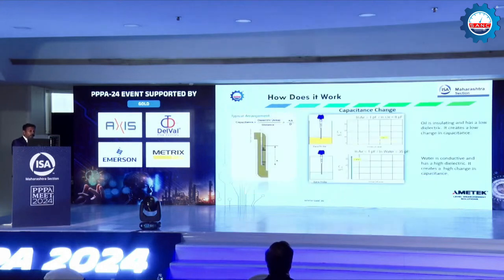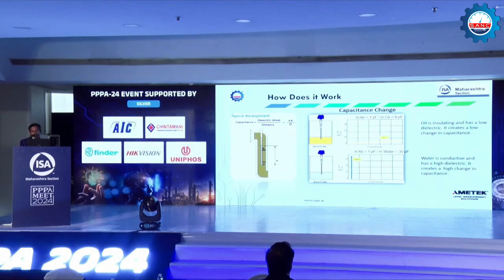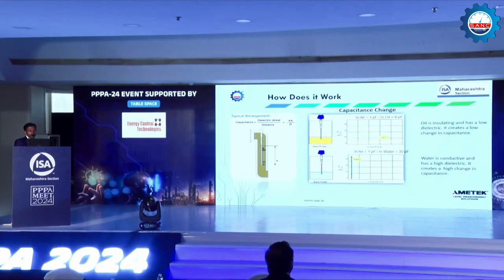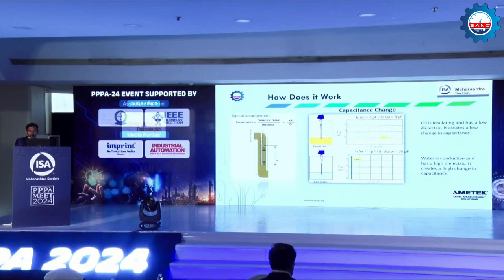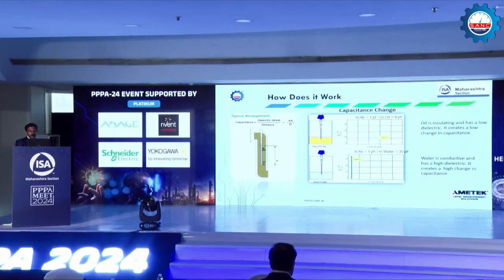How does it work? How are we implementing a level transmitter to measure the water percentage? In a vertical installation, it is the same concept I explained in the desalter: water has a dielectric constant of 80 and oil has only 2. There is a huge difference. In the pipeline, initially the oil is filled, so we measure the capacitance. Let's say in oil we get 8 picofarad. Then we fill this pipe with water, and we get 35 picofarad.